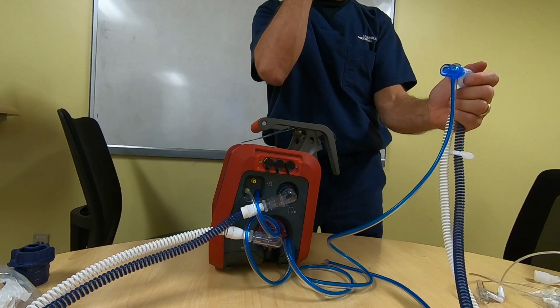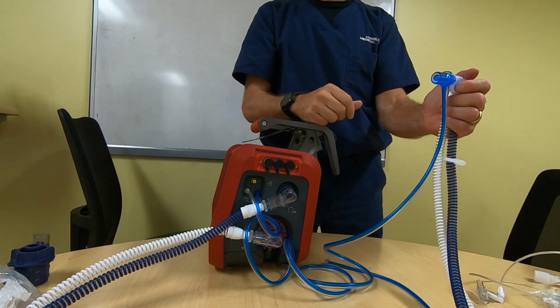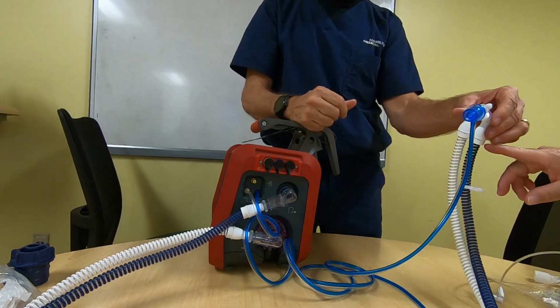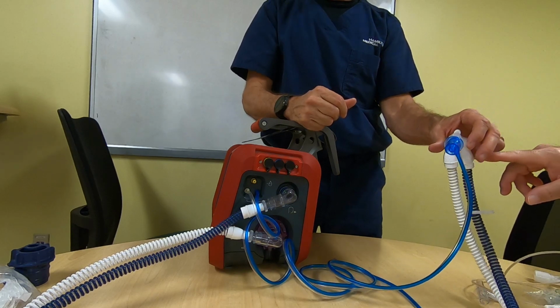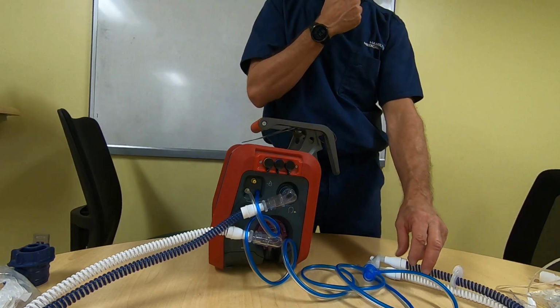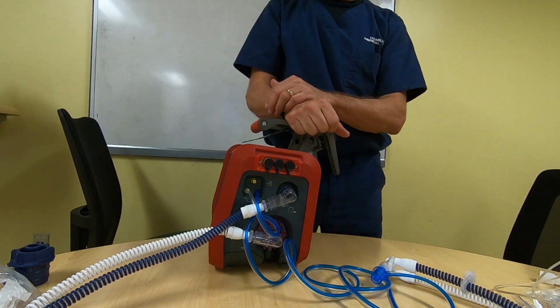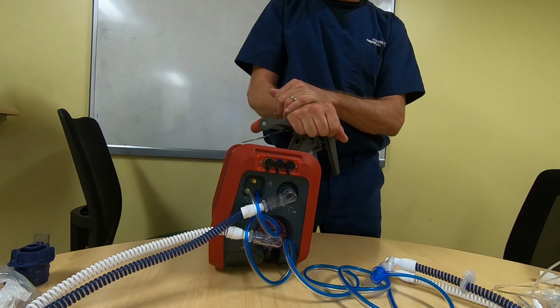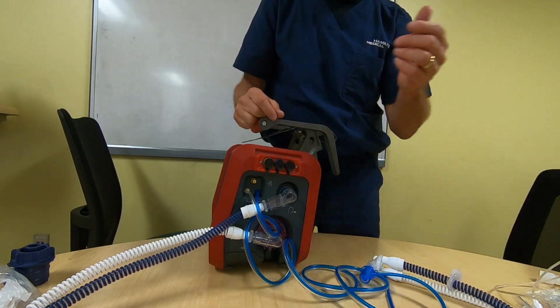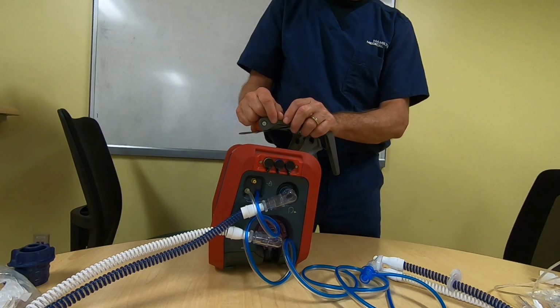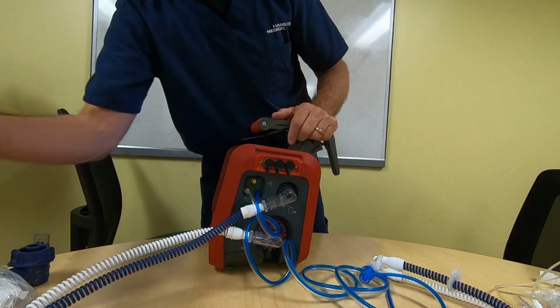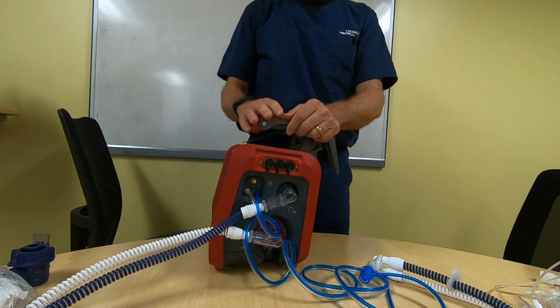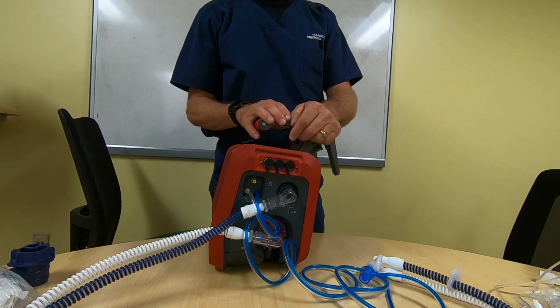With the adult, you guys put it further back? You like right here? Yeah, we're putting it behind all. The sample line we would try to put back, you know, we'd like it 6 inches back, but however we can get it up there. Then the module we're hooking all the way to the back, with about 6 inches of the blue corrugated tubing, that way you have some wiggle room to move things around.